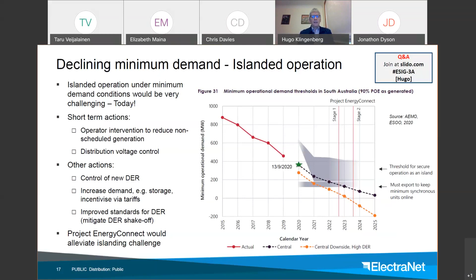On the next slide, I just want to point out that on minimum demand, we looked more at the supply-demand energy balance challenge. However, at a system disturbance level, over the last years, we've learned that for significant transmission disturbances in the Adelaide Metro, that has led to quite a significant sympathetic shake-off of rooftop PVs, to an extent that between ourselves and AEMO, we had to take some action. So good work has been done by AEMO to come up with some DER models that are now being used to update the limits across the Heywood interconnector.